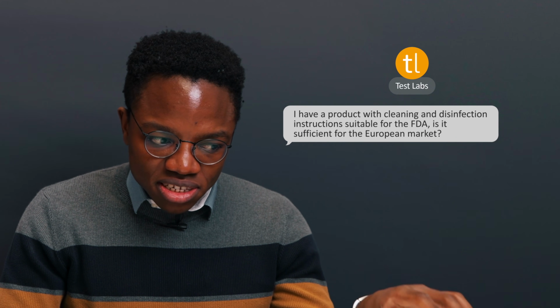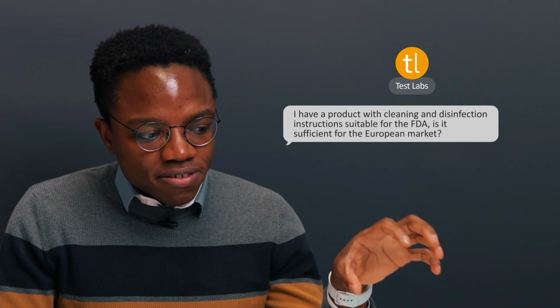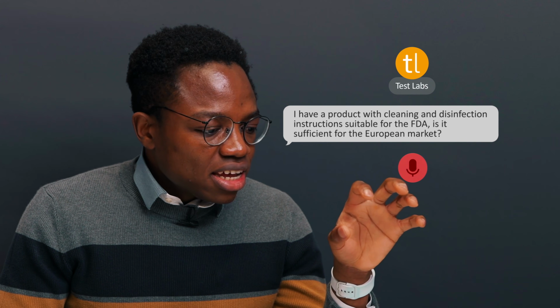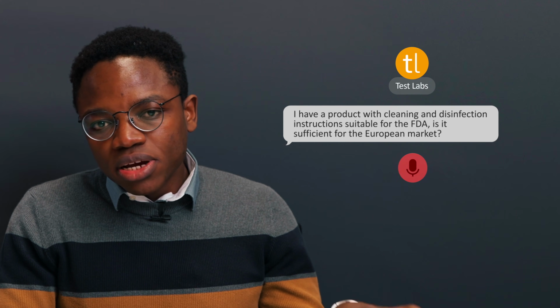The next question is a bit more complicated. I have a product with cleaning, disinfection instructions suitable for the FDA. Is it sufficient for the European market? This is a very nuanced topic, and it's going to heavily depend on your medical device and exactly what you're trying to prove with which market you're trying to be in compliance with. You can be in compliance to both the FDA side and the MDR side, but you're going to need some level of justification within your technical file, as well as some robust evidence to make sure that both sides are happy with what you've done.